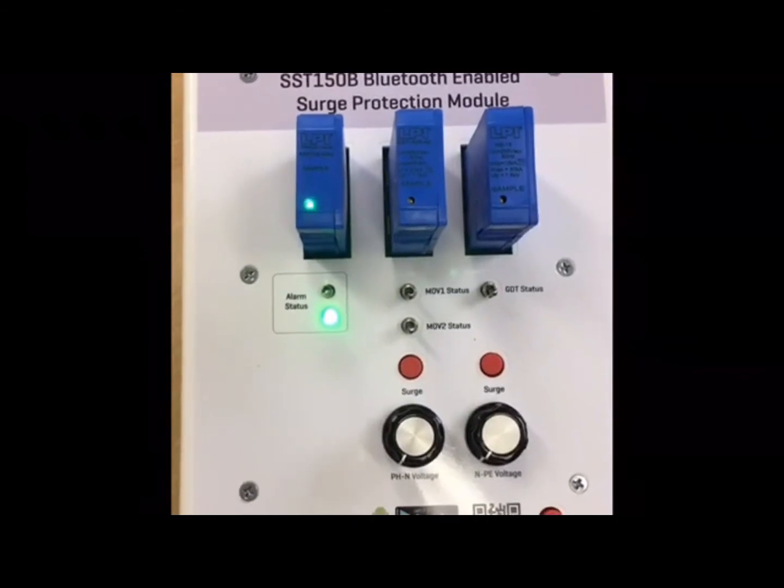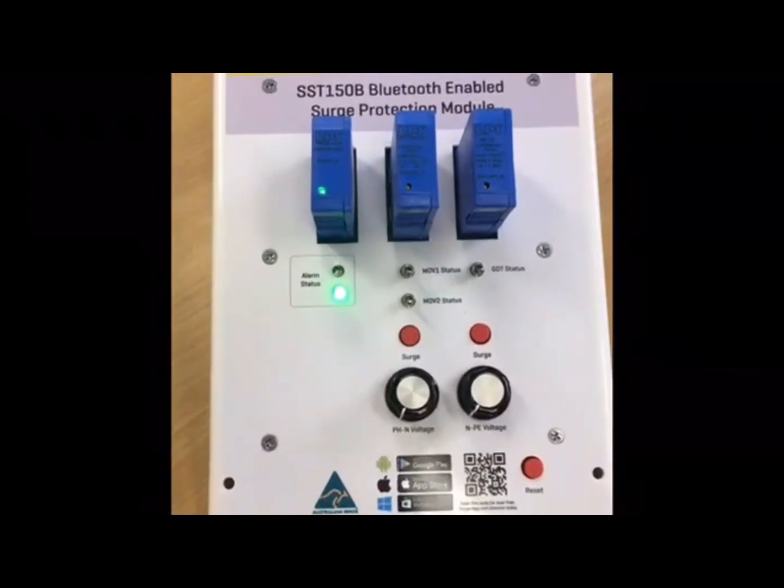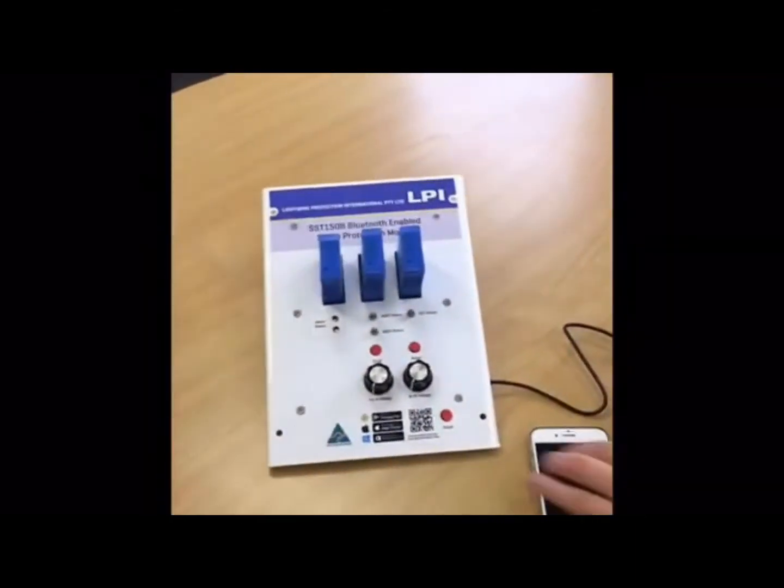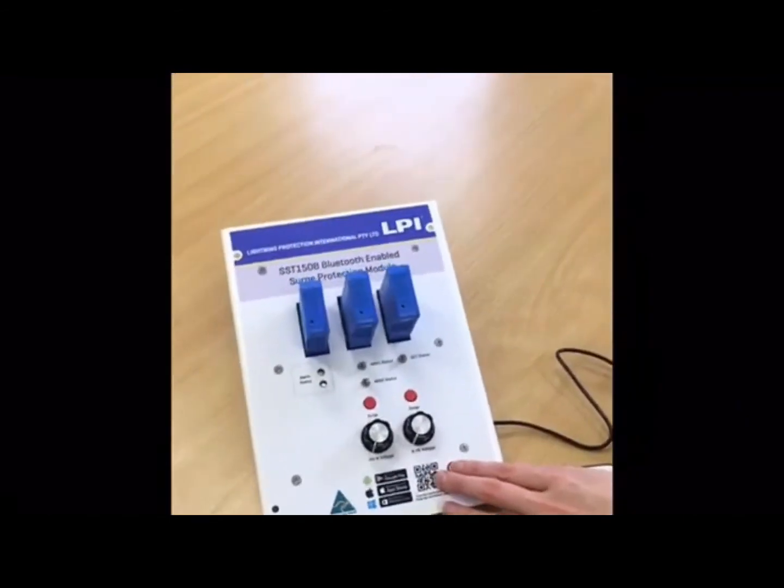To reset information within the SST150B and NE15B, disconnect power and allow a couple of seconds. While holding down the reset button, reconnect the power and allow 5 seconds, then release the reset button. This will clear all values for all units.